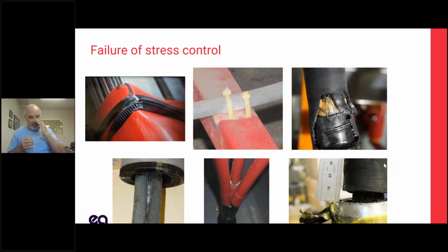And there's a variety of different things that people don't really get on stress control beyond cable terminations. Cables terminate in switchgear typically, or out in the switchyard. But in the switchgear, there's a lot going on. If you look at some of these pictures, here are things that people do every day and don't give a thought. How many of us use tie wraps? I've got a car I think is held together with tie wraps, and it pulls tight, and it causes a concentration of field. The permittivity of a tie wrap is different than the permittivity of air, and different than that of plastic. So these things that we take for granted can cause PD.